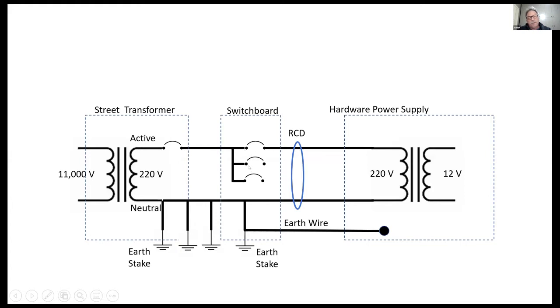The neutral is connected to earth at multiple points, including in your own switchboard, with a cross connection between the neutral and the earth. Then you'd probably have an RCD - or in the UK I don't know what you'd call them now, ELCBs or safety switches, they go under different names. Here's the earth down the bottom, the earth wire going to the metal panel, and the black dots represent a stud connecting to the metalwork.